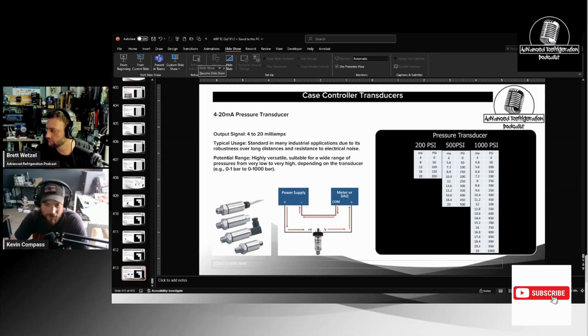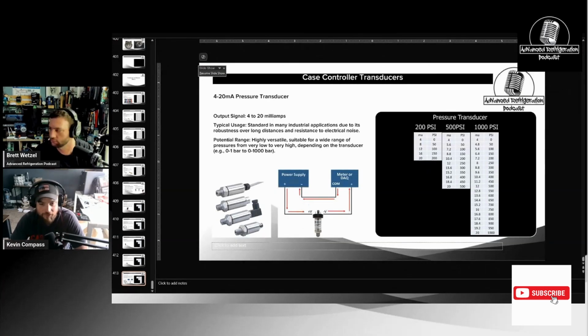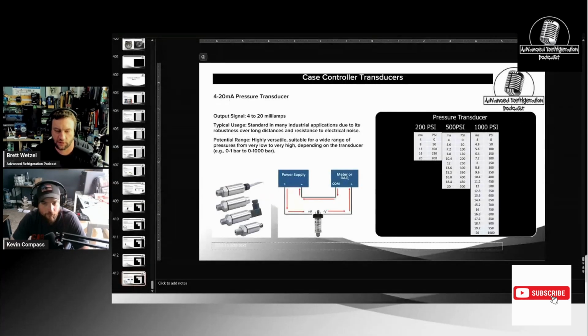So you have your power supply, then you have your input. Now, the outlet of the transducer, meaning your voltage out, which is going to be your negative, is going to go to the signal in of the device, so the positive side of the device. Now, the bad part about this is you can't just put your meter on common and positive of whatever device it is. Now the whole thing's gone.